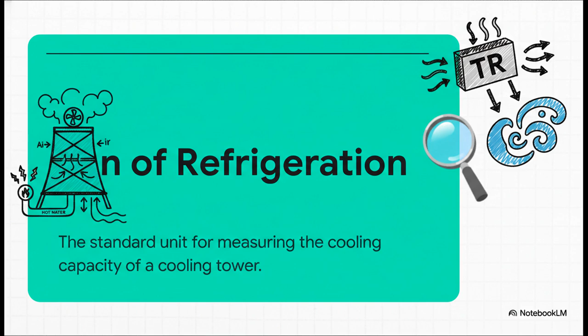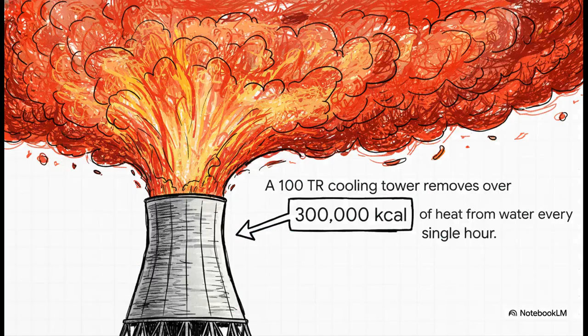So what does that really mean in terms of energy? Well, 1 ton of refrigeration is officially defined as the power to remove 3,024 kilocalories of heat every single hour. And to put that number into perspective, even a pretty modest industrial cooling tower might be rated at 100 TR, meaning it's powerful enough to pull over 300,000 kilocalories of waste heat out of that water every single hour. The amount of energy being managed is just absolutely staggering.